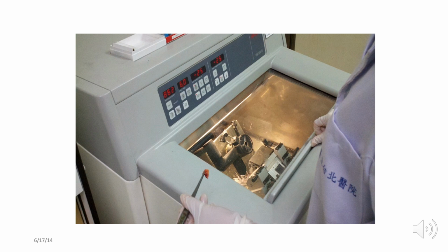And what do you notice? You have there a built-in microtome within the cryostat, so that after freezing the tissue, you will immediately do the sectioning. So you are actually skipping the other procedures, the dehydration, clearing, embedding. From fixation using the compressed carbon dioxide, you can immediately go to sectioning by using the cryostat. So you have a microtome inside a refrigerator-like apparatus, and the name of that refrigerator-like apparatus is the cryostat.